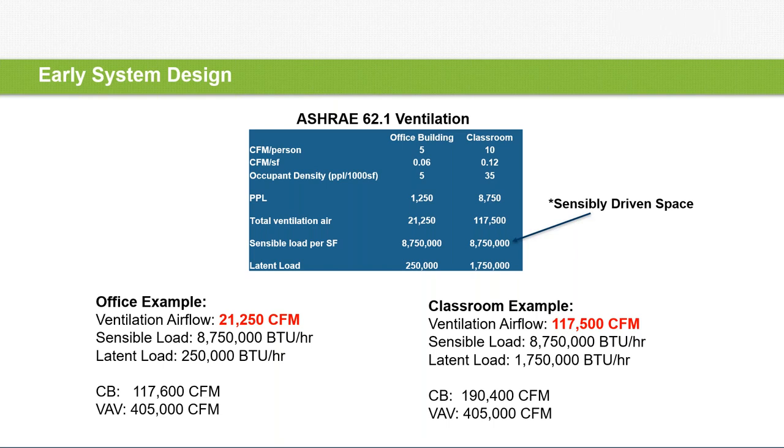So that's driving one part of the conversation. So now you know what to size. And what I actually found with these, it kind of surprised me, was that both of these scenarios were driven by the sensible load. What I mean by that is that the airflows were driven up by the amount of sensible load we had to treat.